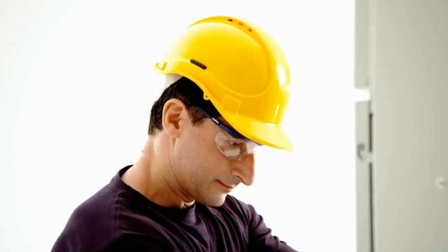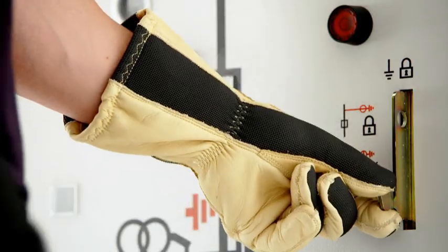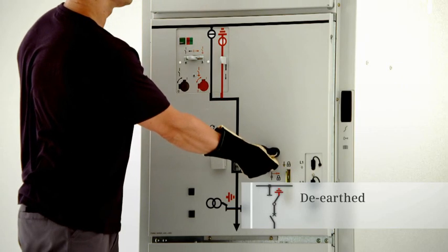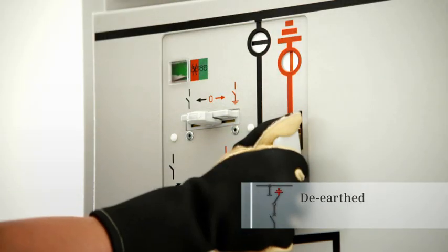To de-earth this feeder, the padlock must first be removed rendering the locking device inoperative. The circuit breaker can then be switched to the open position and hence the feeder can be de-earthed.